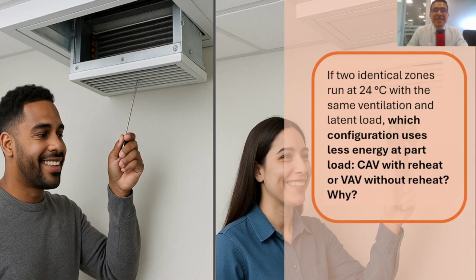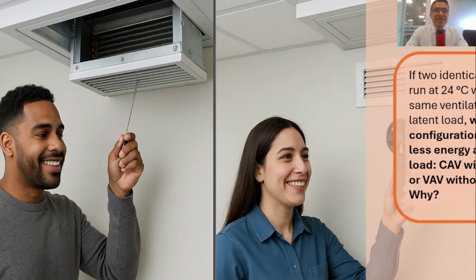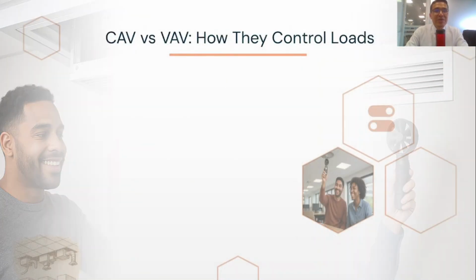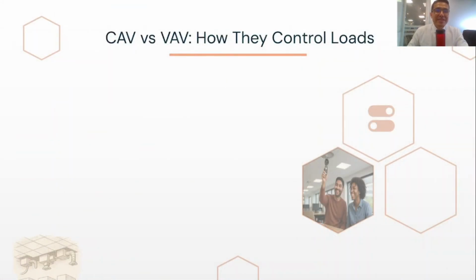Reflect on this: CAV energy stays flat for the coil and increases for reheat, and the VAV energy tracks the sensible load until reheat is needed at the minimum flow. So think about all of this, and we will explain more concepts in this video.